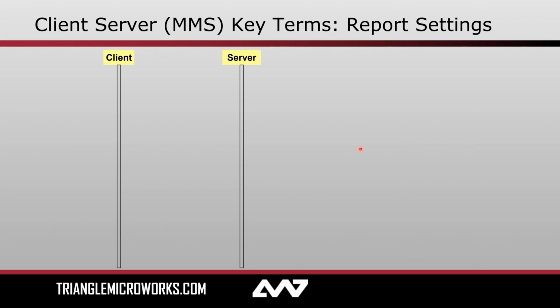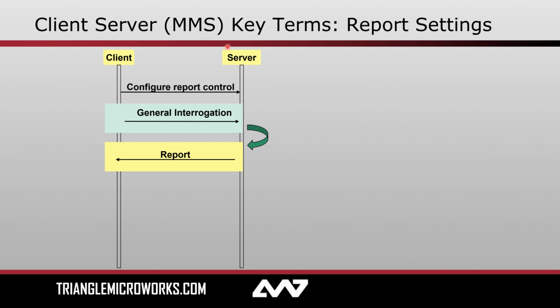So what are the mechanisms for actually getting data out of those report control blocks? Well, the first step is the client is going to configure the report control block. This effectively means enable it and reserve it. Say, hey, you're available, I want to go ahead and say that I'm going to be grabbing your data. Next, the most basic way, and this isn't really an event-driven method, is a general interrogation. This is initiated by the client. And in that case, the server goes ahead and sends back all of the data in the report. You could think of this as kind of a cousin to the read that we spoke about before, because it is initiated by the client. And all data in the report, every single value in that data set, will be sent back to the client. So it can find out what the value is of everything at that given point.